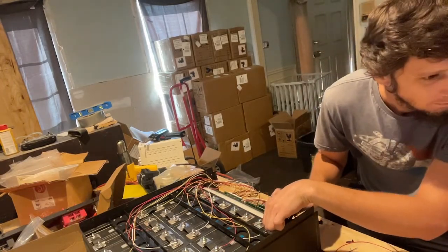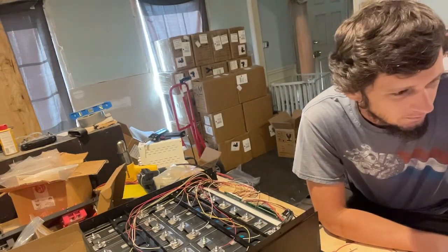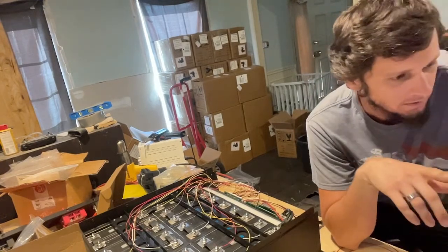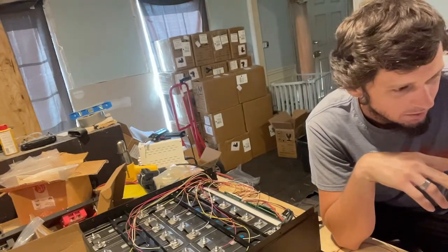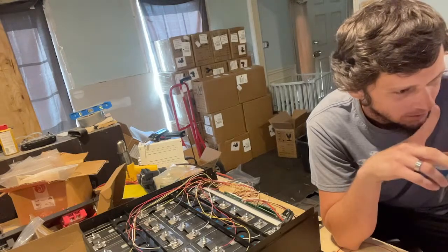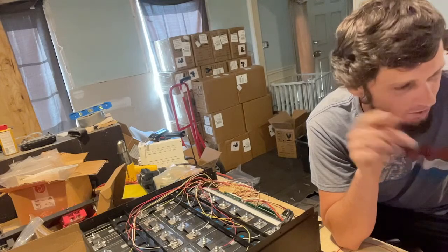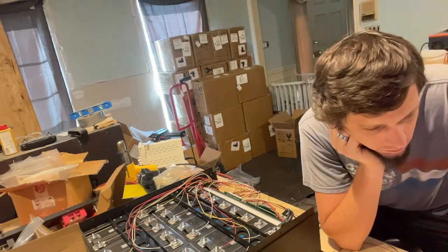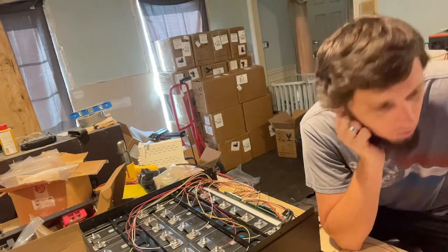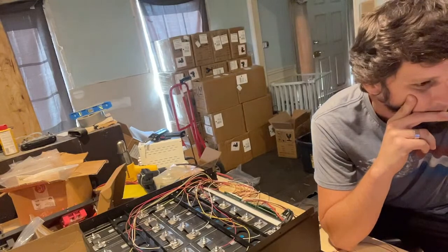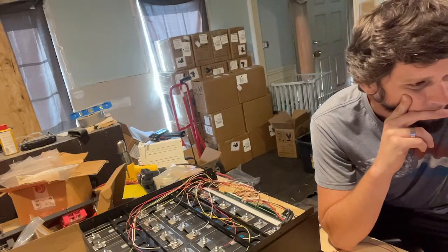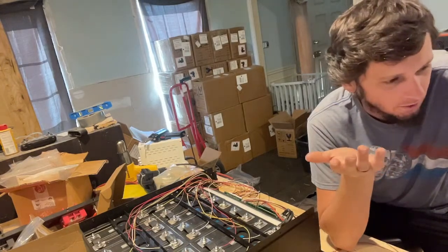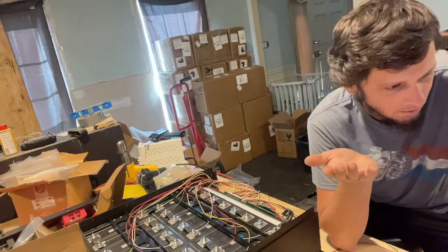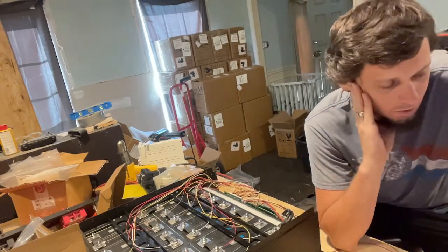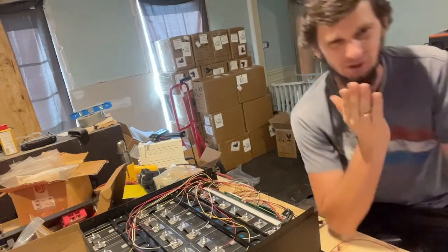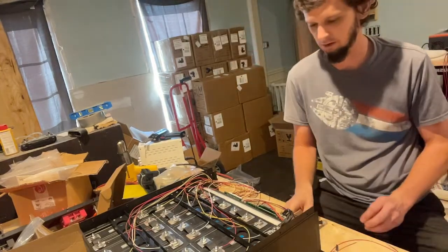So the setup uses a 2-gauge butt splice from Amazon, two 7-gauge into a 2-gauge extension on the 304 amp hour cells with 2 bolt holes. I just installed two 6-gauge lugs. Six-gauge lugs for the 7-gauge wire, right—yeah, that makes sense. You're kind of stuck with the double 7-gauge from the BMS, you can't change that, so you may as well jump up to 2-gauge or so. Since you're using a 200 amp BMS, 2-gauge makes sense.